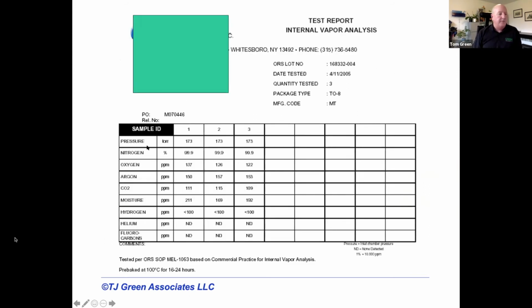This is a typical RGA report. Now, moisture is the big worry, but there are other gases in here that tell a lot about your process. Just a couple of years ago, we spec'd out not only a moisture limit, but an oxygen limit and a limit on perfluorocarbons down at the 50 ppm level.